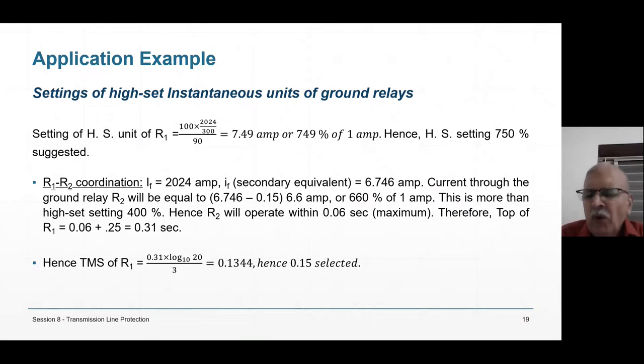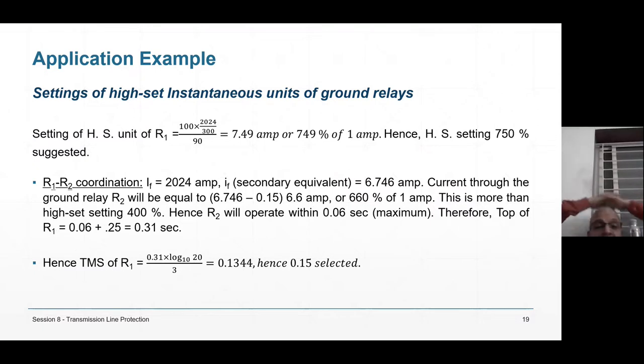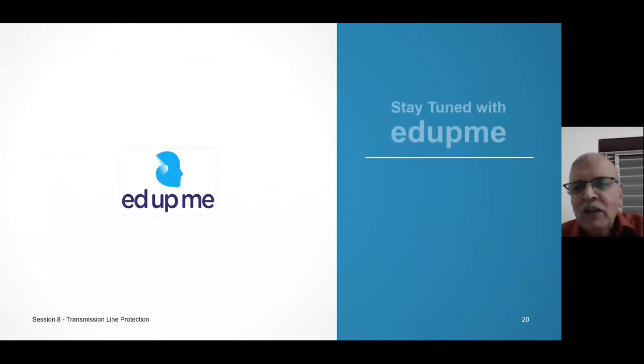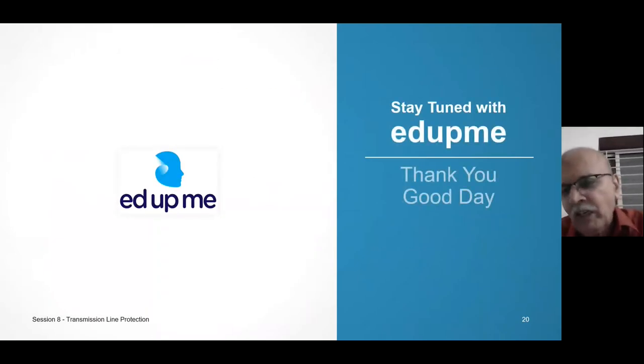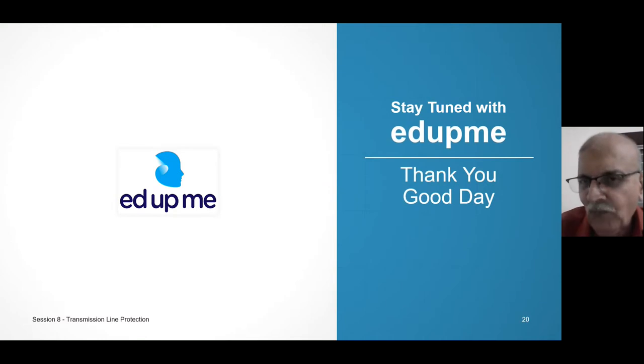So, formulas are the same. The construction is also the same. But the philosophy of relay setting calculation is different in ground relays. So, you have to take care about ground relays. Having told about that, my friends, we come to an end of our examples of earth fault relays.